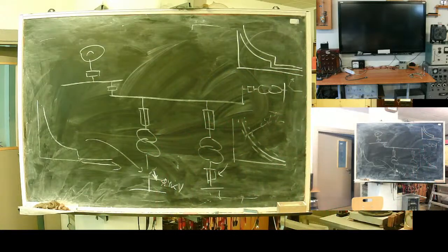In fact, an unreliable thing. Really unreliable. With time, these tiny nozzles have a tendency to be clogged. So relays fail. Also, strangely, with time, oil, since they usually came in a set with the oil switch. With time, it's observed, strangely how it happened, but oil got into these chambers. You open it and there's oil inside.